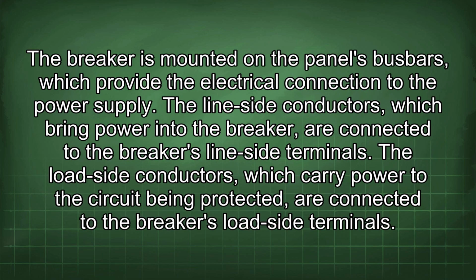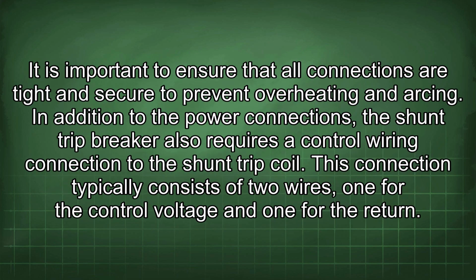The breaker is mounted on the panel's busbars, which provide the electrical connection to the power supply. The line-side conductors, which bring power into the breaker, are connected to the breaker's line-side terminals. The load side conductors, which carry power to the circuit being protected, are connected to the breaker's load side terminals. It is important to ensure that all connections are tight and secure to prevent overheating and arcing.